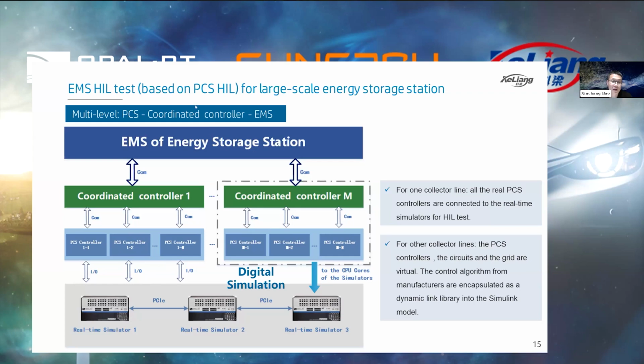Based on the PCS hardware-in-the-loop setup, we can connect a real coordinated controller to the system. The coordinated controller communicates with the 15 PCS controllers via a communication protocol, sending different commands to the PCS controllers under different test conditions.